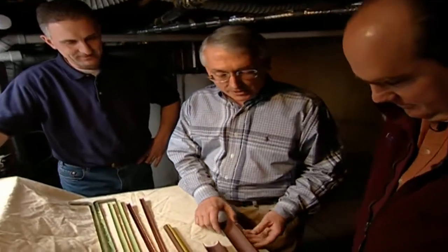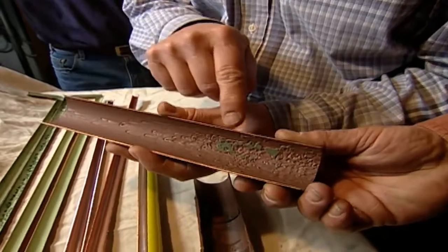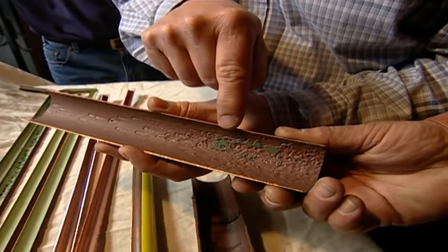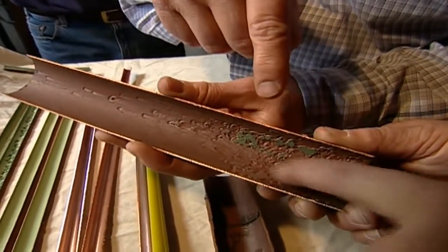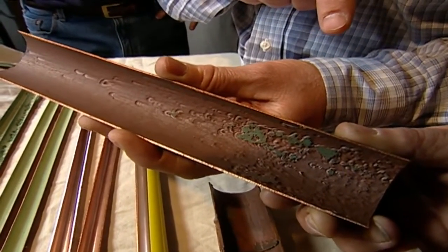Another possibility is high velocity and erosion corrosion. This is an example of that problem. The green material is the film. It has been eroded away. Look at how it's just completely... Right, there's little horseshoes where the water velocity has removed the material.